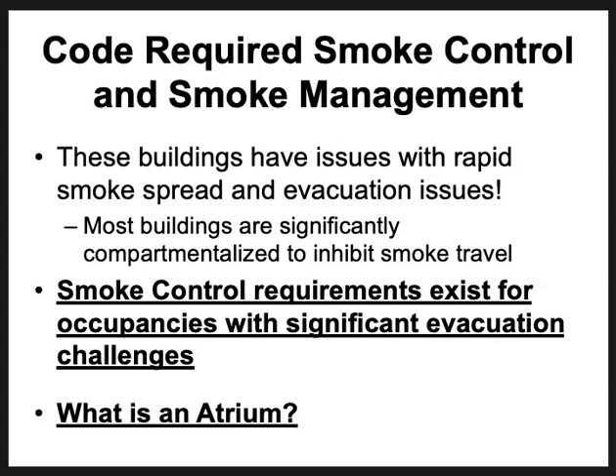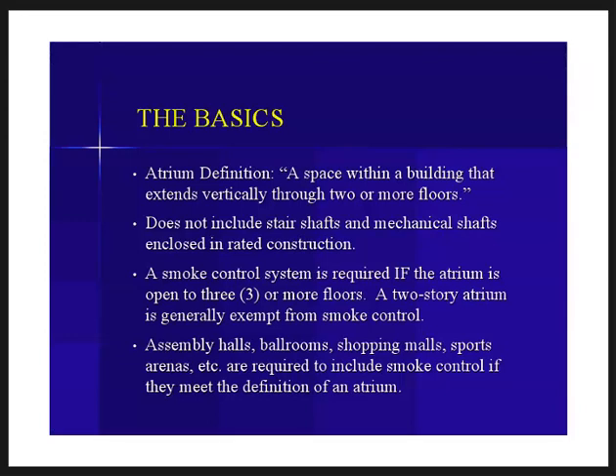Smoke control helps them with that. Now, most of the buildings we just talked about, what they have in common is an atrium. Not all of them. All of them have evacuation challenges, but most of them have atriums. So what is an atrium? Let's make sure we all understand that. An atrium is any kind of building or space within a building that extends vertically through two or more floors. So that doesn't include stair shafts and mechanical shafts that are enclosed in rated construction.